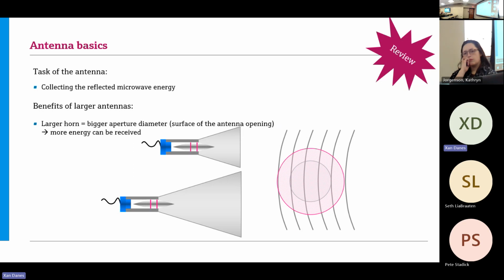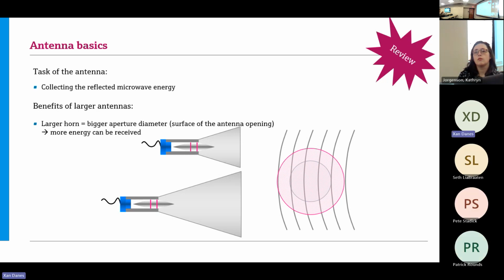Traditionally I was taught that for every nominal increase in antenna size - say going from 1.5 inches to 2 inches, or 2 to 3 inches - I effectively double the available gain of the measurement. So with larger antennas of a radar at a given frequency, you often get narrower beam angles but also larger measuring ranges, and in some cases larger measuring ranges with fluids of lower dielectric constants, meaning less reflective media.